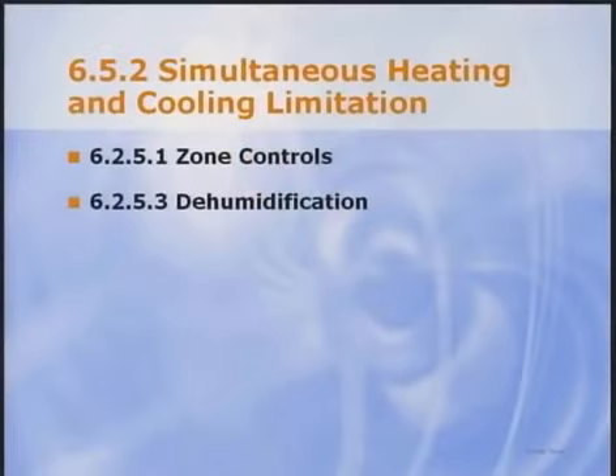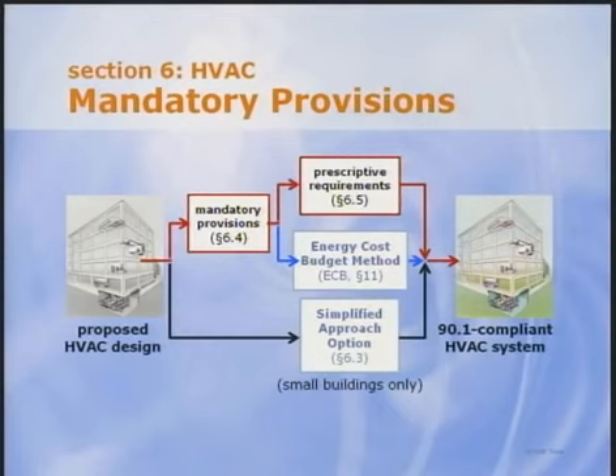In looking at ASHRAE 90.1, it has limitations on simultaneous heating and cooling. There are two sections that we'll cover today: zone controls and dehumidification. We'll go through the dehumidification section first. Unlike the demand-controlled ventilation requirement in high occupancy zones, which is mandatory, these limitations on simultaneous heating and cooling are prescriptive. That means that if the project is following the prescriptive path, they are required.